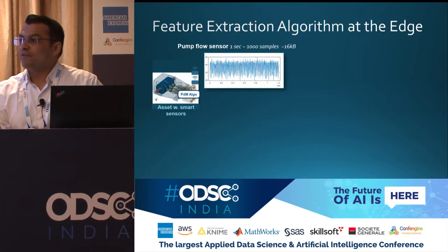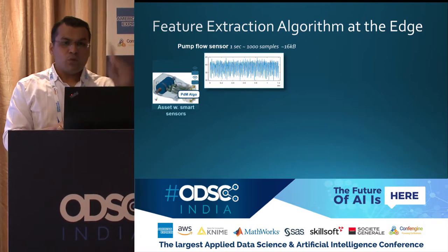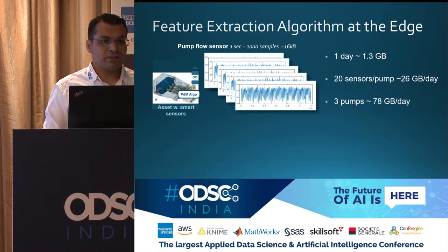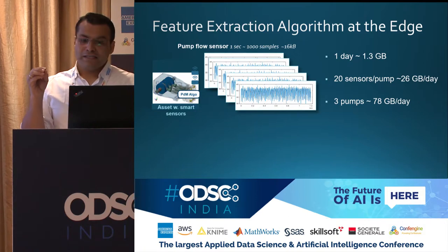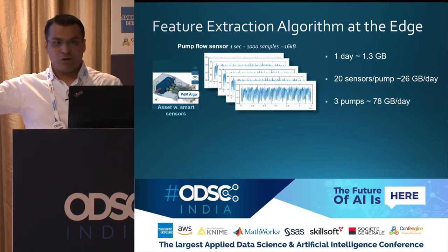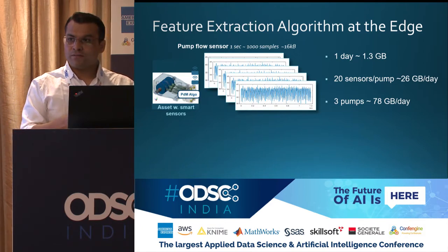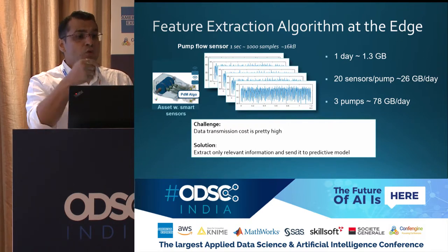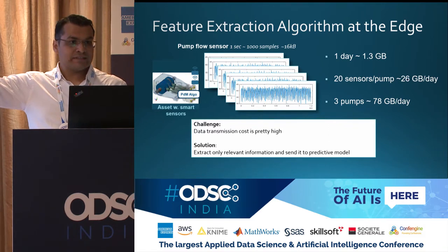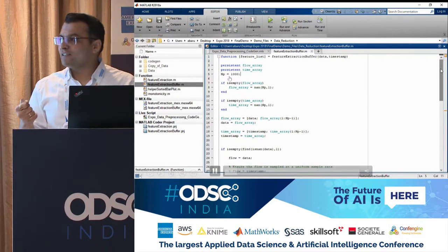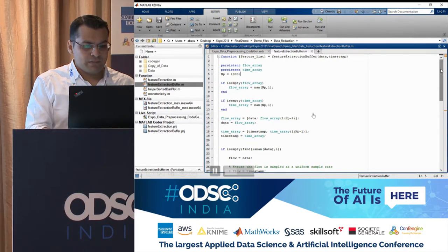Why is it important to take feature extraction directly on the edge? If this is a pump with one sensor taking measurements at every millisecond, I'll be getting 1000 samples which is 16 KB. If I do it for an entire day: 1.3 GB. If I have three pumps and 20 sensors, we'll be generating 78 GB of data. Does it make sense to send all the data unprocessed, pay a lot of money on transmission? You'll be checking bandwidth as well as cost. So on the edge itself, clean the data, extract what is useful, and send what can be consumed by your machine learning algorithm. I'm creating a buffer of 1000 samples — it doesn't make sense to take mean on every single point. Wait for 1000 samples, take a mean, and then extract those features.